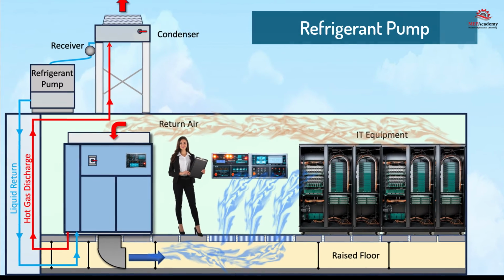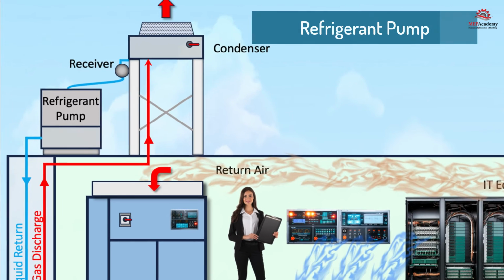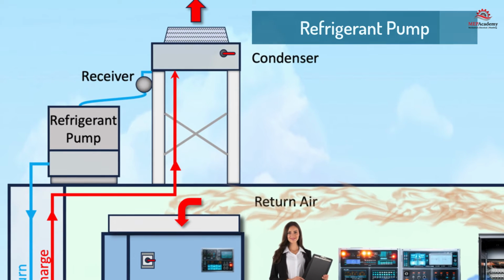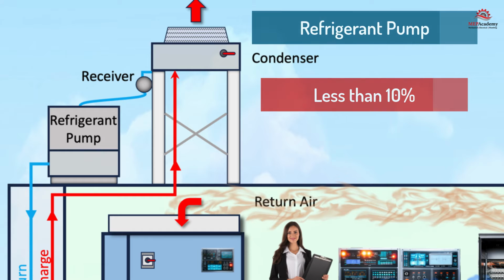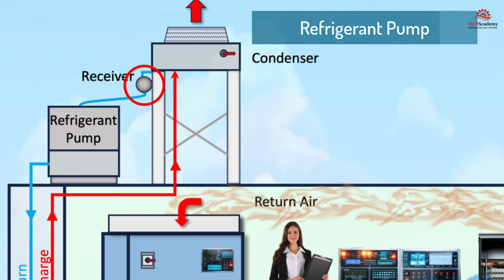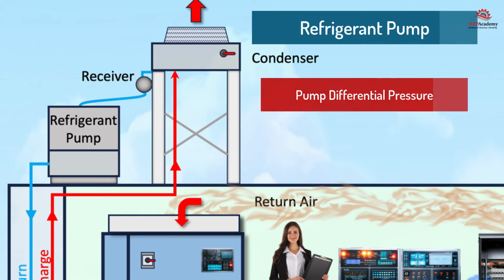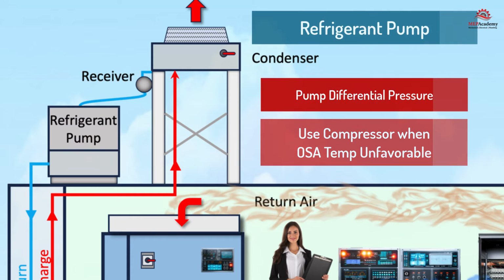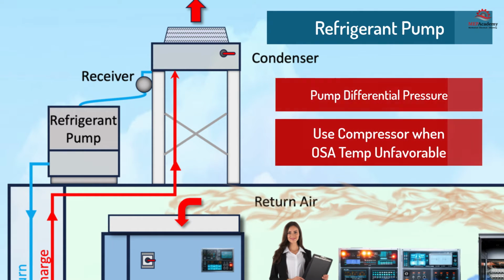Refrigerant pump. The heart of the refrigerant economizer is the refrigerant pump. This isn't the compressor, but a separate pump used to circulate the refrigerant during economizer function. Pumps use less than 1/10 the energy of a compressor, allowing for energy savings. The pump is located below the receiver and condenser. The pump takes the high side subcooled liquid, leaving the condenser, and moves it to the expansion valve while maintaining a differential pressure for proper operation. When outside air conditions are unfavorable, the compressor comes on and the pumps are bypassed.